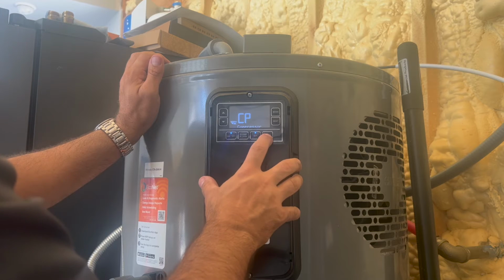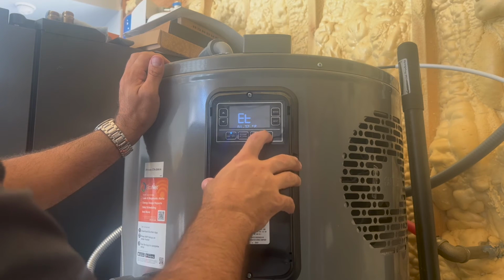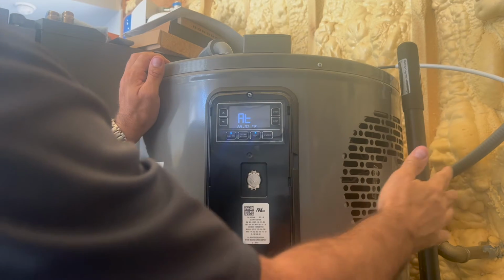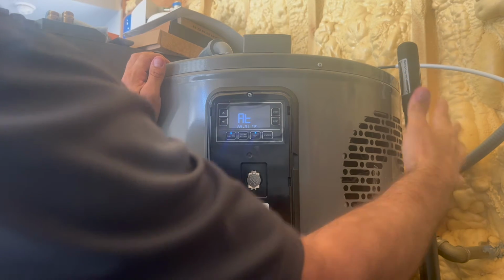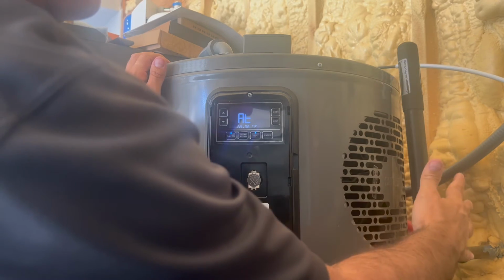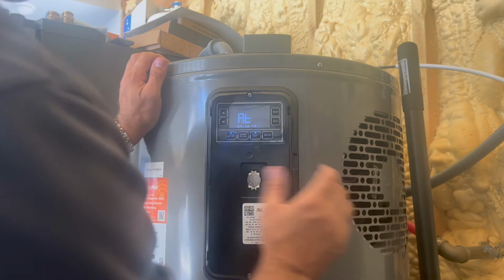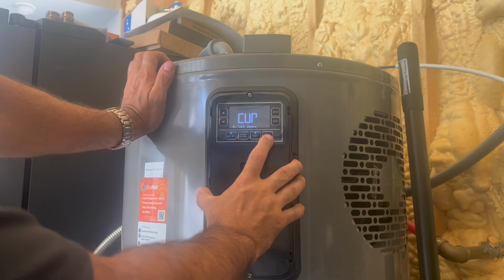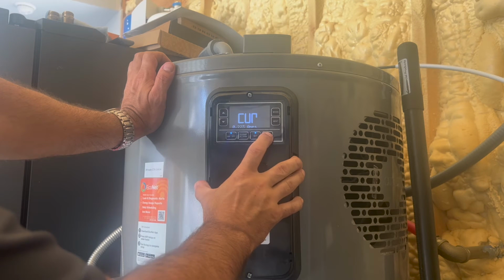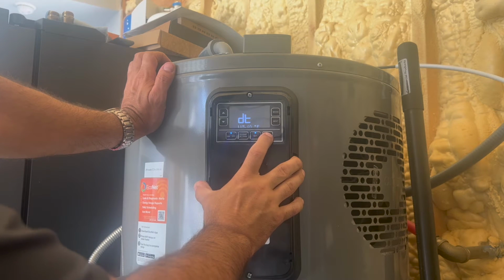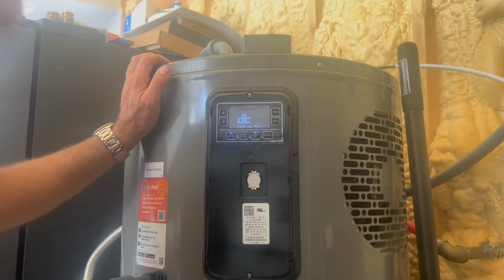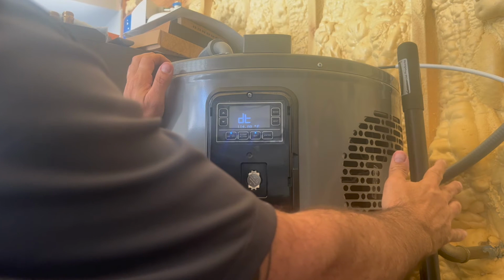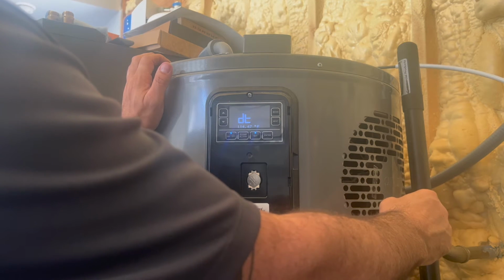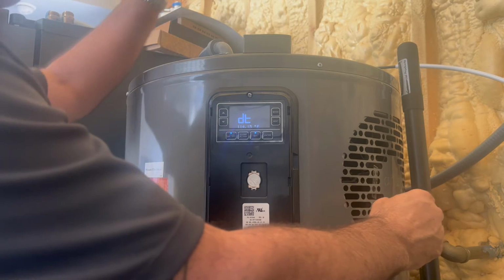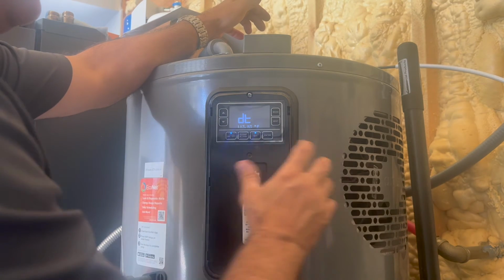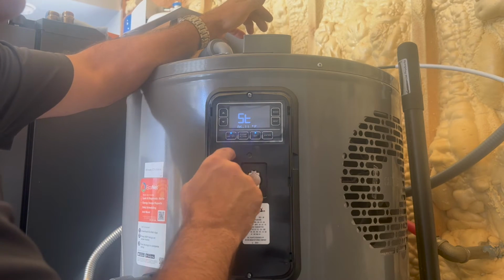Now I know that thermistor is working because I know it's about 90 degrees in here. So, what does that tell us? It tells us that if this evaporator is removing heat, that I should feel cool air coming through here. Cooler than 90, and I do. Current amp draw, we're gonna give this thing a minute to ramp up here. Okay, discharge temperature. Discharge temperature is what's gonna heat our water. It's at 115 degrees. Suction temperature is 86 degrees.